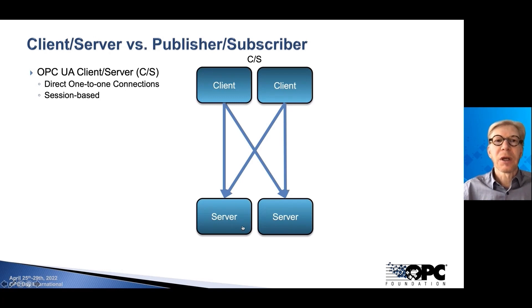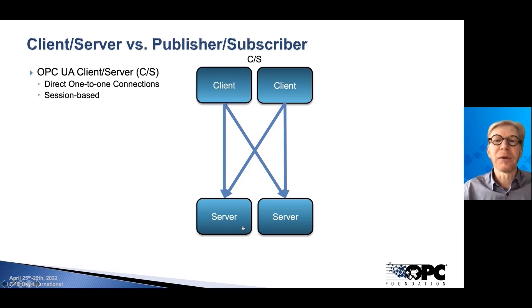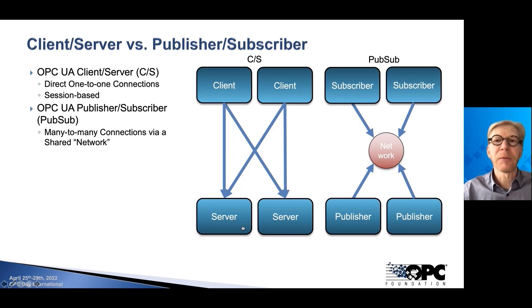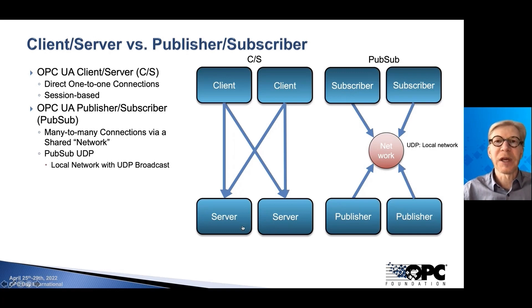In the traditional OPC UA client-server, we're talking about direct one-to-one connections between applications. One acts as a server, the other acts as a client. The major thing here is that these connections are always session-based. The session has a lot of advantages — we can authenticate the applications with each other, and in all further communication we know who is communicating with whom. In the new publisher-subscriber model — PubSub as we call it — we're talking about many-to-many connections, where all participants, publishers and subscribers, connect to a common network.